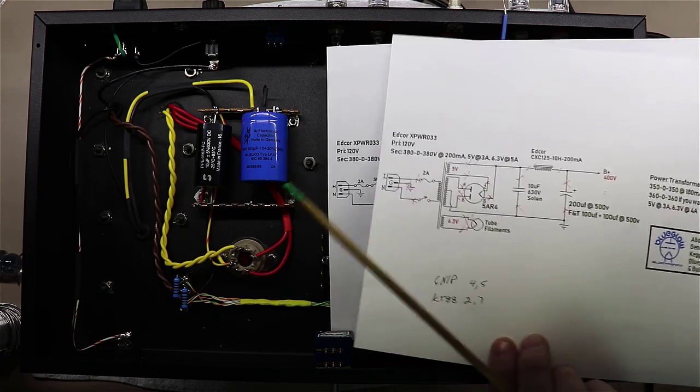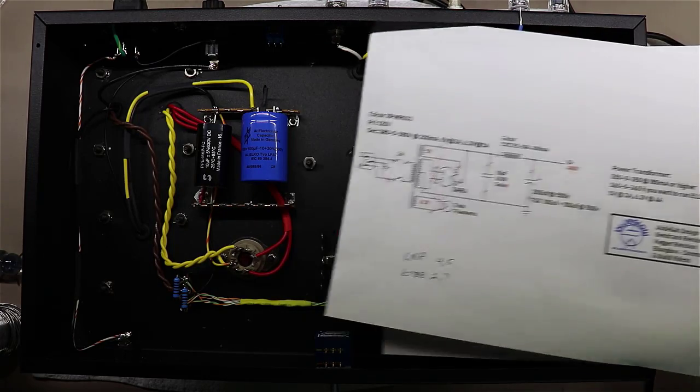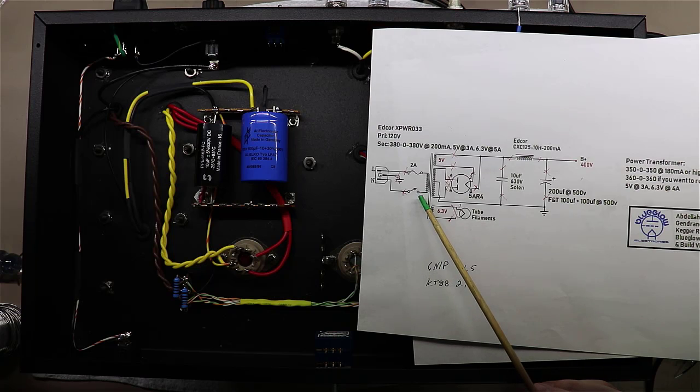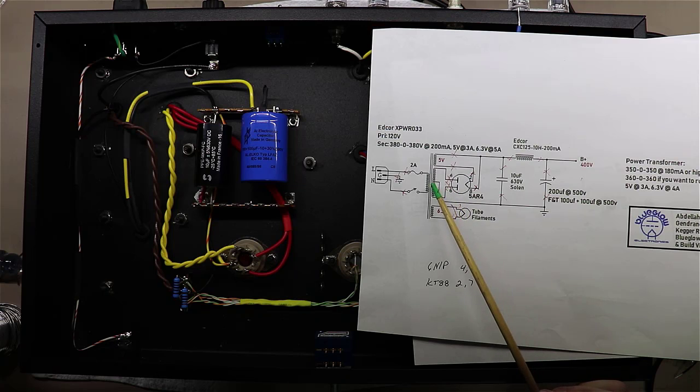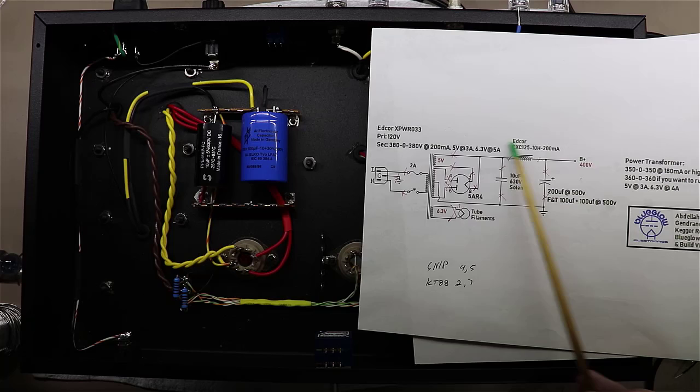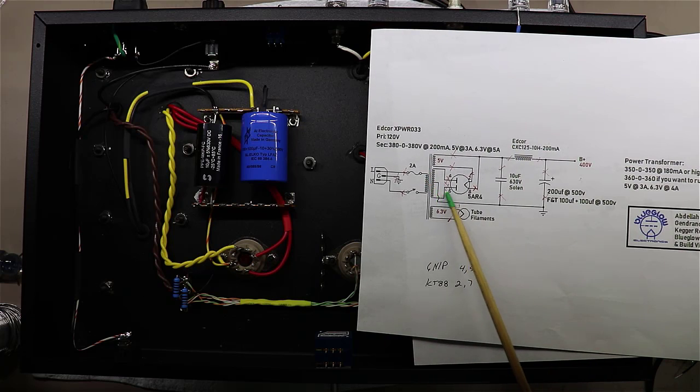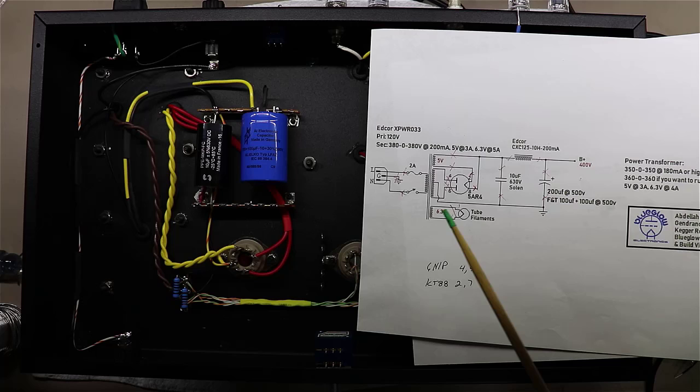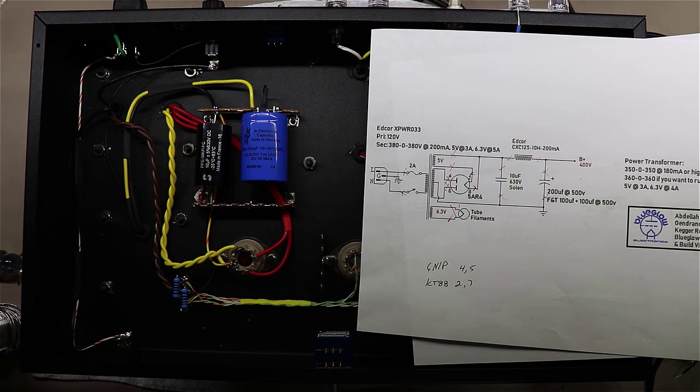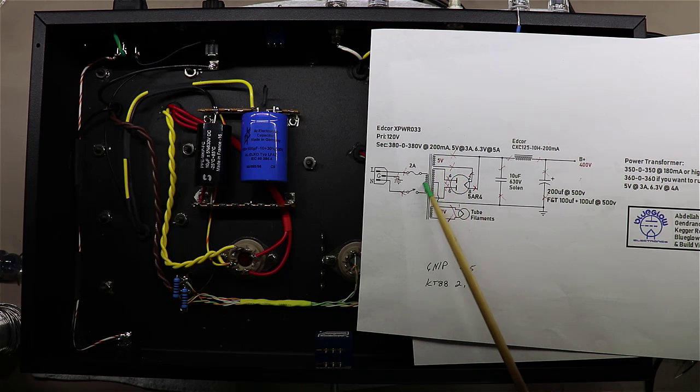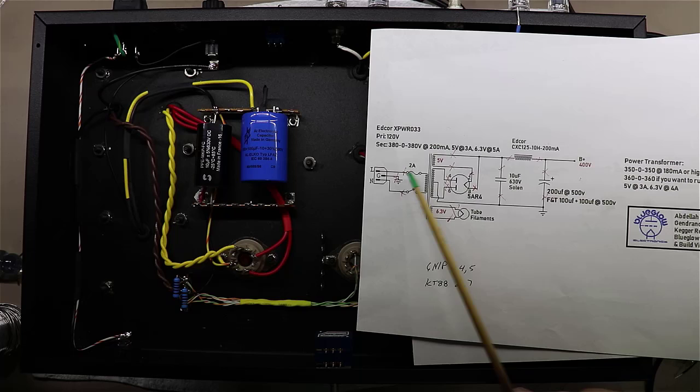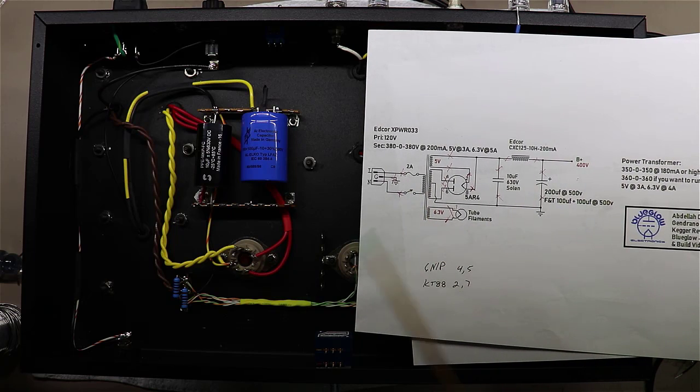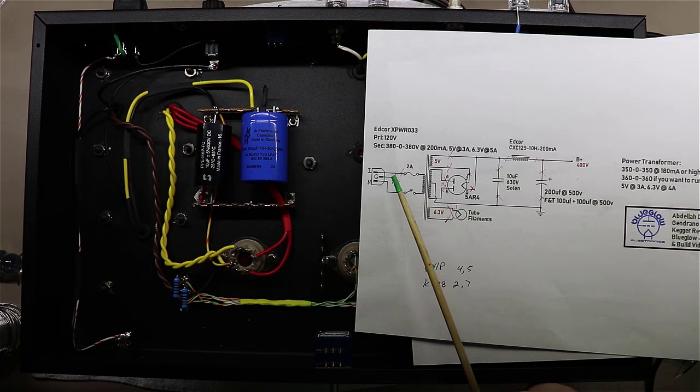The reason for this is if you're switching the neutral side and for whatever reason you have a short somewhere in your transformer or whatnot, you can actually make the chassis itself live with respect to ground. So if you grab something else in your house, maybe a faucet or something else that just happened to be grounded and this thing was turned off, you still have a live current flowing in here and you could potentially get shocked. So it's always a better practice to switch the hot wire.